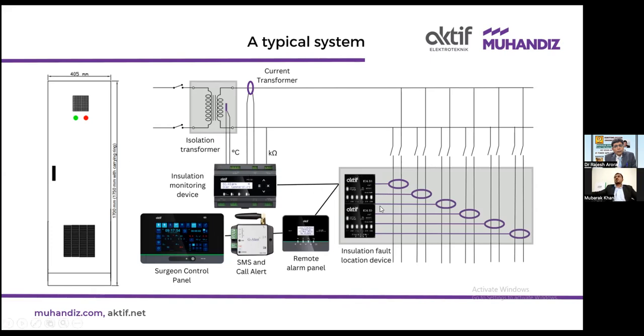Then there is a fault location device. Before discussing fault location, coming to the insulation monitoring device, it measures the resistance of both phase conductors with respect to ground in real time, and it will display the values. If the resistance value goes below 50 kilo ohm, it will give an alarm. This is as per the NEC standard. Now we have a fault location system. When the insulation monitoring device gives an alarm that there is an earth fault somewhere in your system, this fault location system will automatically detect which particular feeder is having a problem.